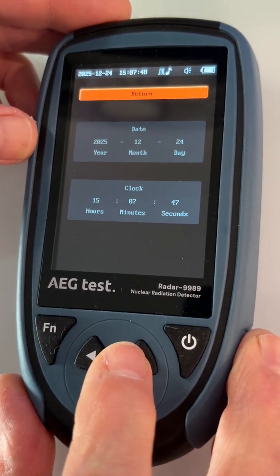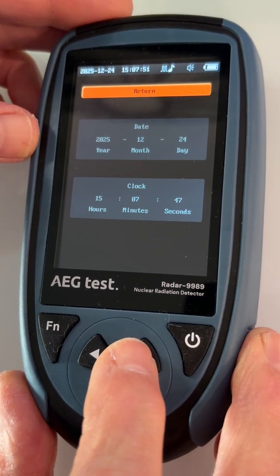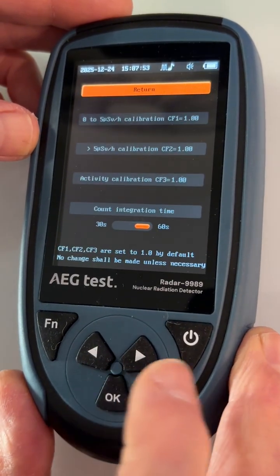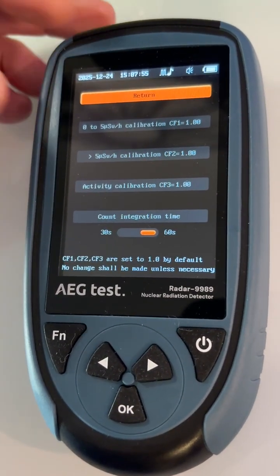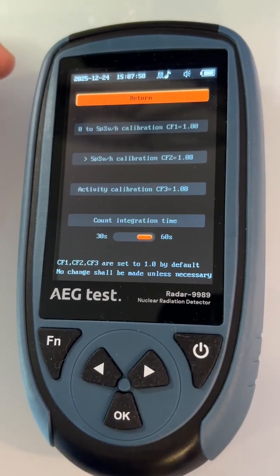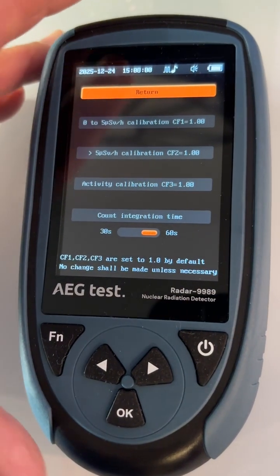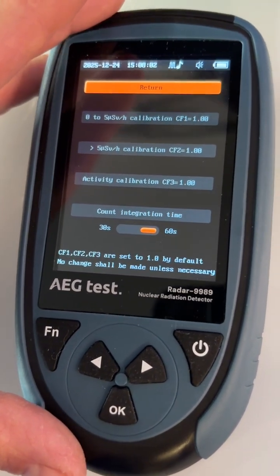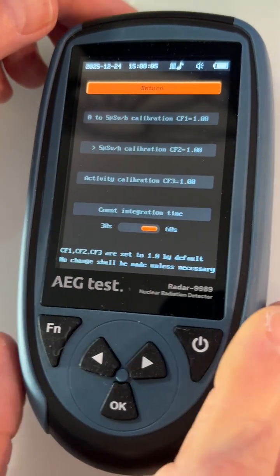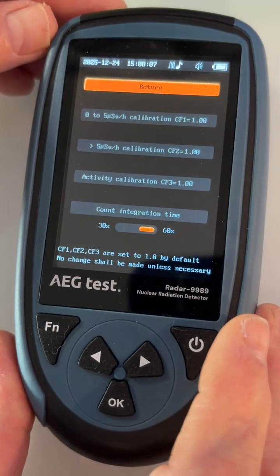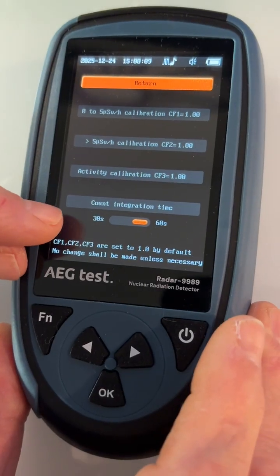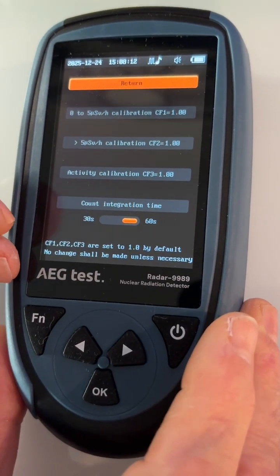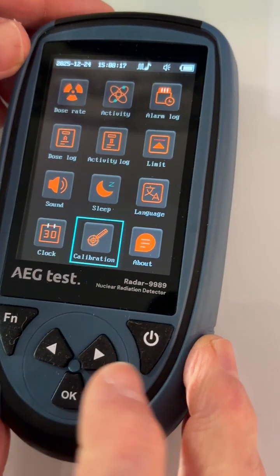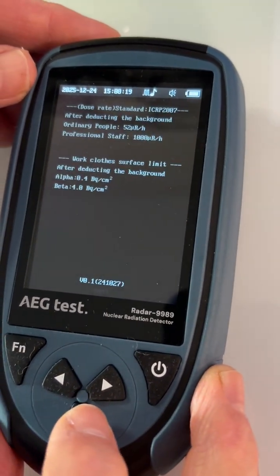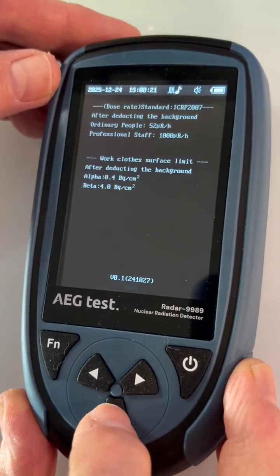Got the basic clock function where you set the time, whatnot, and the date. It's got a calibration function. The manufacturer does not recommend you go in here and do anything. If you do, you may mess up your instrument. But it is made available for those that need to use it. It is there. The integration count rate is also set here. It's set to 60 seconds, the same as another instrument which I'm going to show you here in a minute. And of course the about function, just information on the instrument.